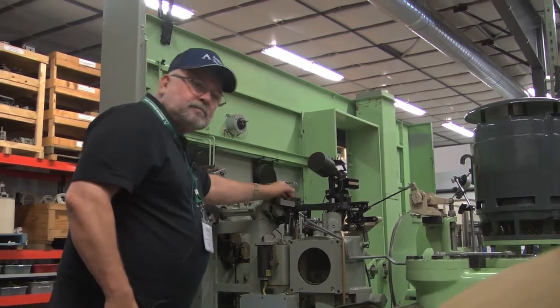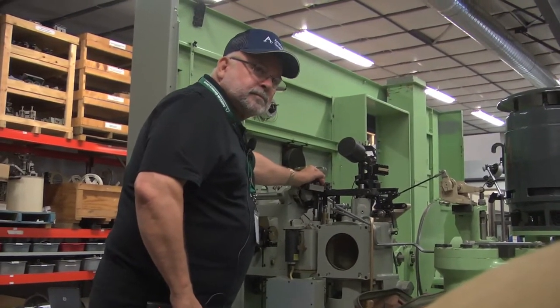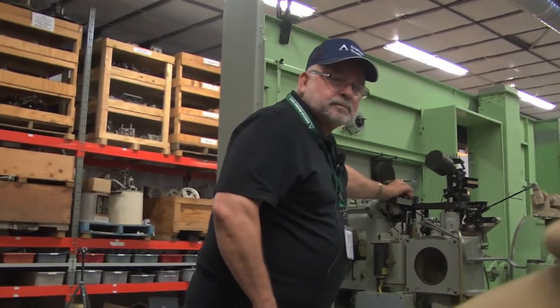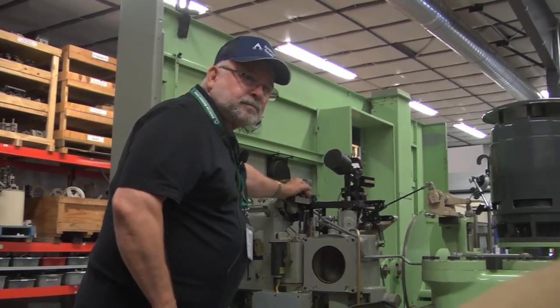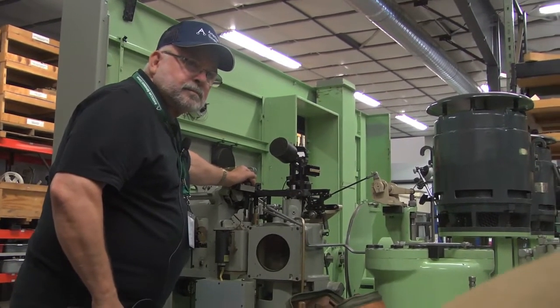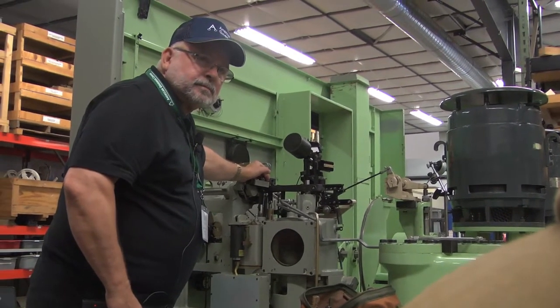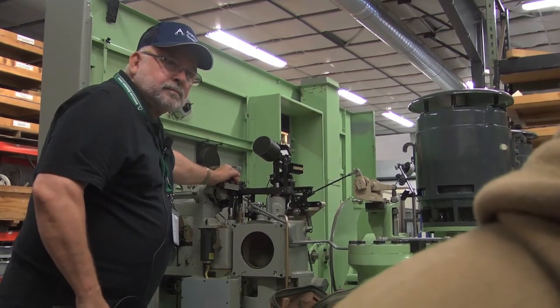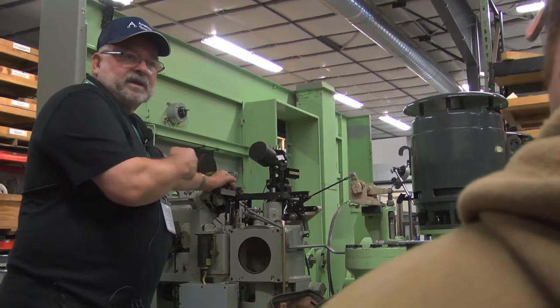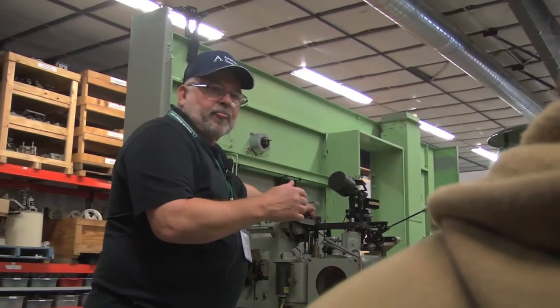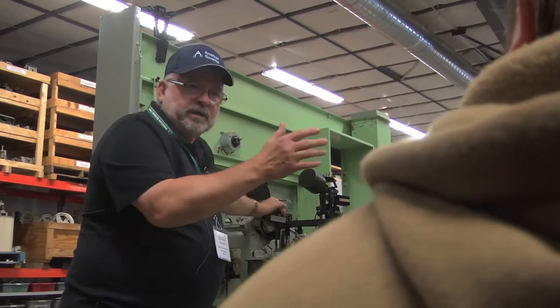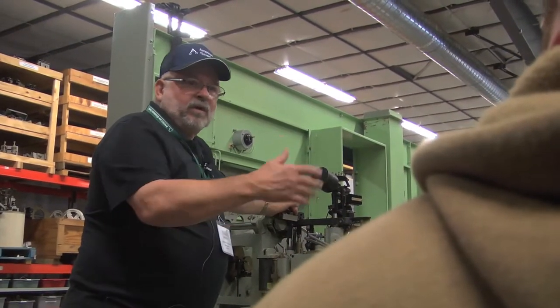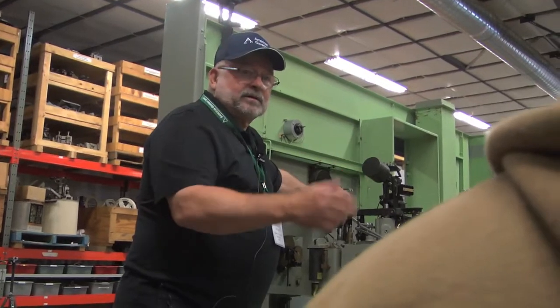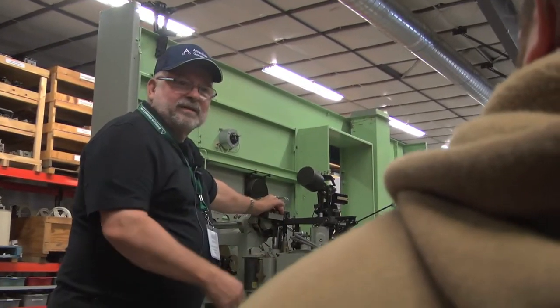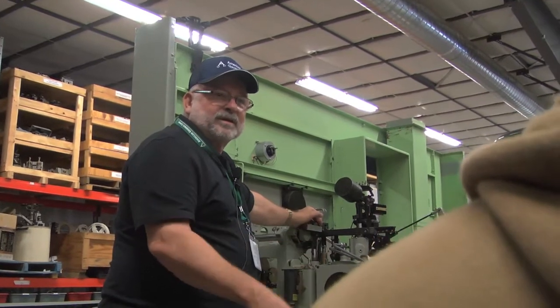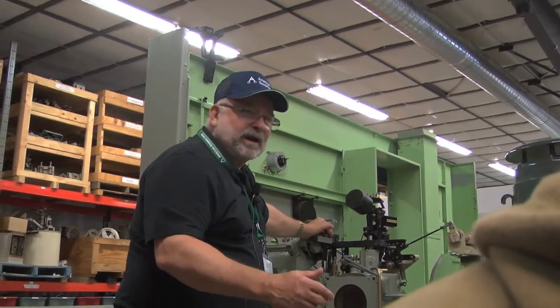One thing I noticed, you guys were talking about breaker signals, like the shutdown solenoid, the 33 switches. I thought that was just something, but those numbers are pretty constant for Pelton. Yeah, because they tied into all of those. 43 is our auxiliaries. Yeah, they kind of match the industry. Okay, like a 12X, you know, everything. An 86 is a complete shutdown, you know, a lockout relay. All right, so when they say you're 86'd out of a bar, can't go back.